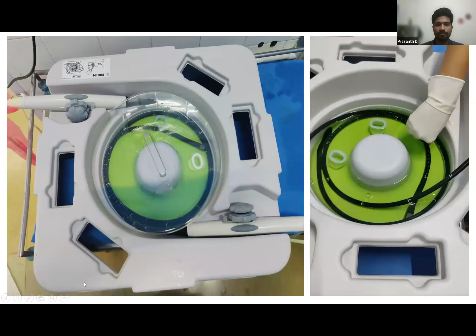The content is 2.45% glutaraldehyde Cidex solution. You have to keep both the bite guard and the flexible shaft of the TEE probe inside, and allow it to stay for 20 minutes. After 20 minutes, we have to remove it and rinse again with water. As Cidex is a chemical, it will cause irritation for the next patient. So you have to clean it with running water for about a minute, rinse, and dry it completely.